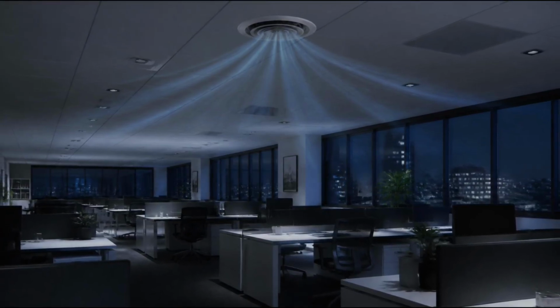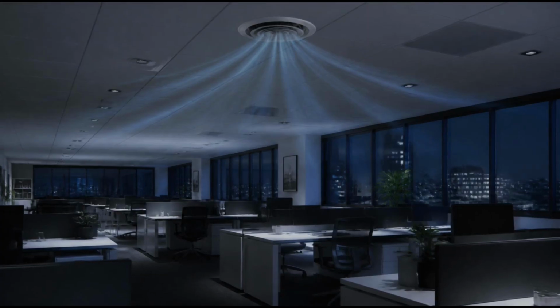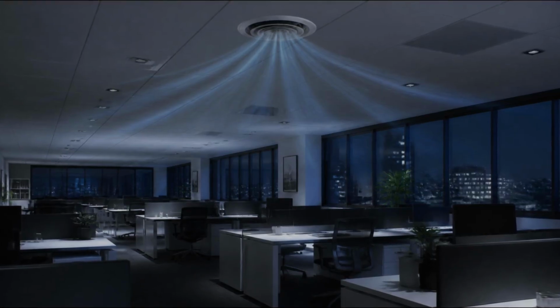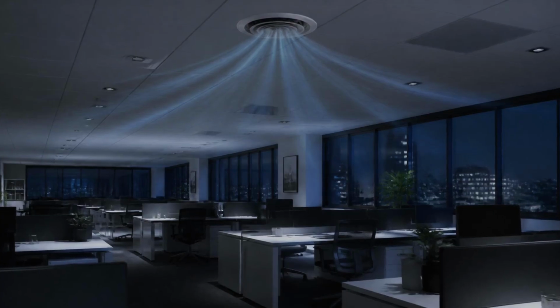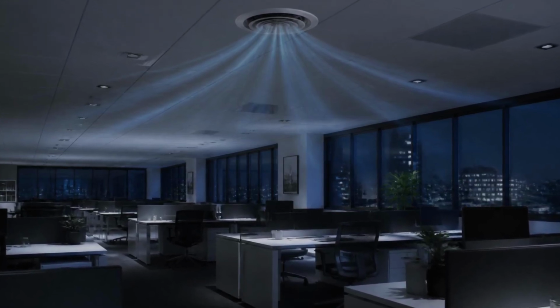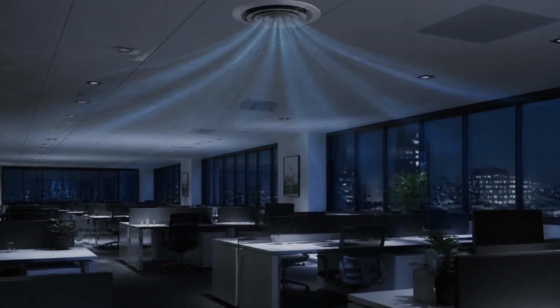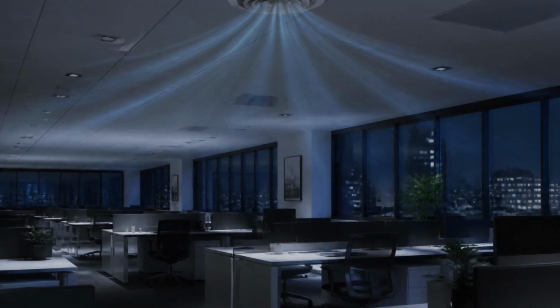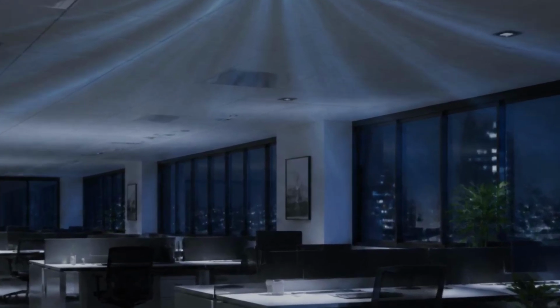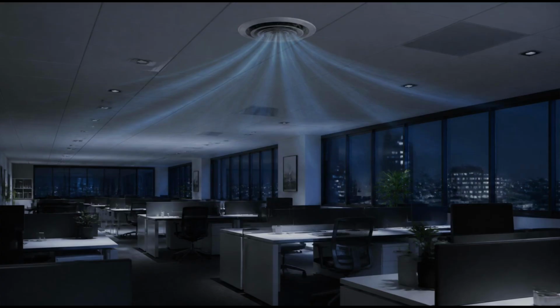A zone that receives too much supply air can be adjusted. A return pathway that draws too strongly can be balanced against its neighbors. The overall effect is a building in which air moves calmly and predictably from where it is delivered to where it is collected. Balanced pressure helps air move in the right directions. The result of all this careful management is a building that simply feels right to be in. Rooms are neither stuffy nor drafty. Corridors feel calm. Air quality is consistent from one area to another. The temperature holds steady. There are no mysterious cold drafts or inexplicable warm pockets. The pressure balance is doing its work quietly in the background.